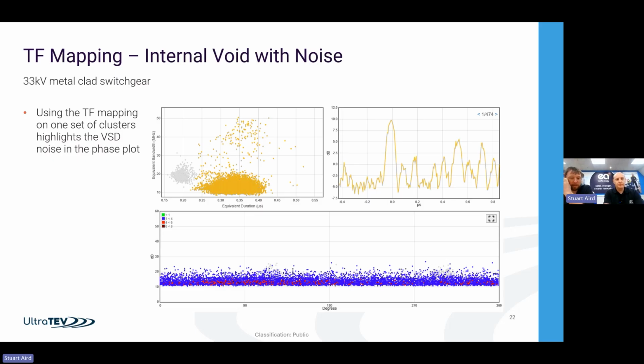This is looking at the pulse shape effectively, the energy and the frequency content of that energy, the rise times, the widths, allowing you to see pulses that look different to each other. The top right element is looking at around 500 samples within that area, allowing you to flick through and see what those waveforms really look like.